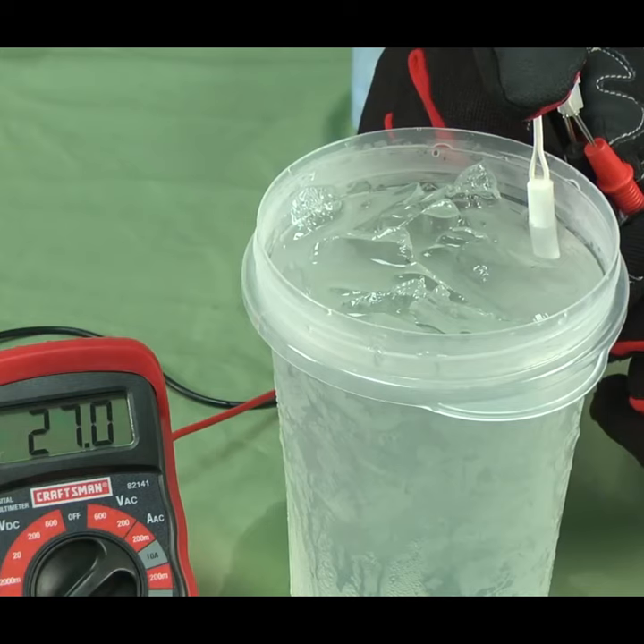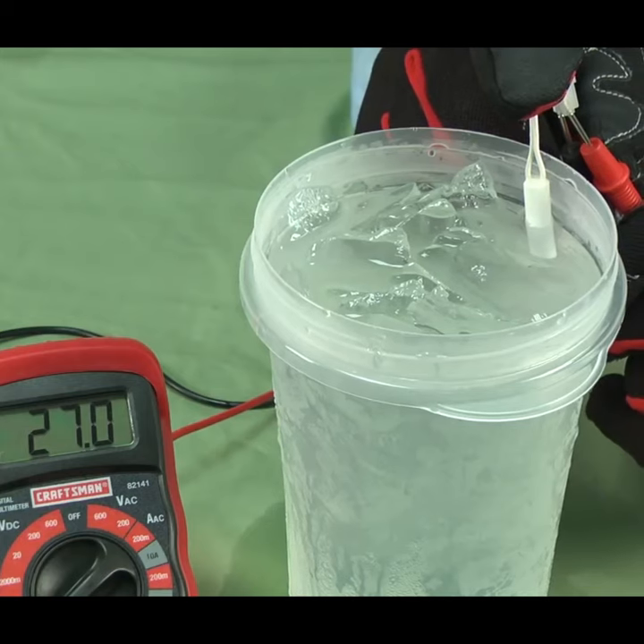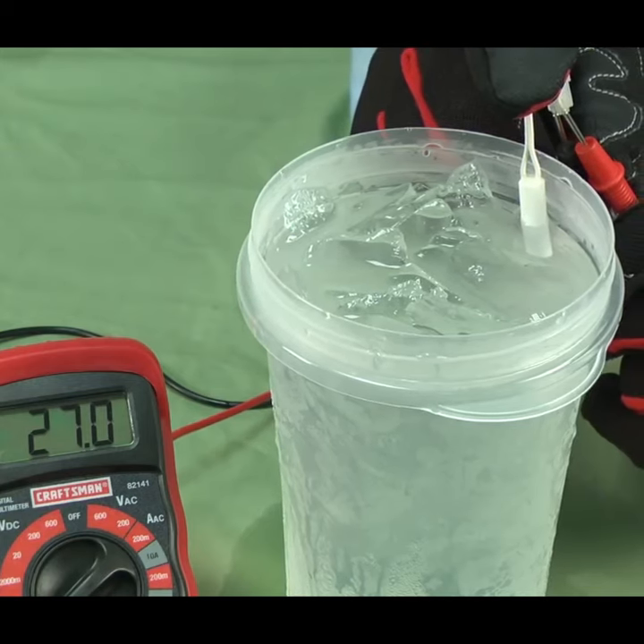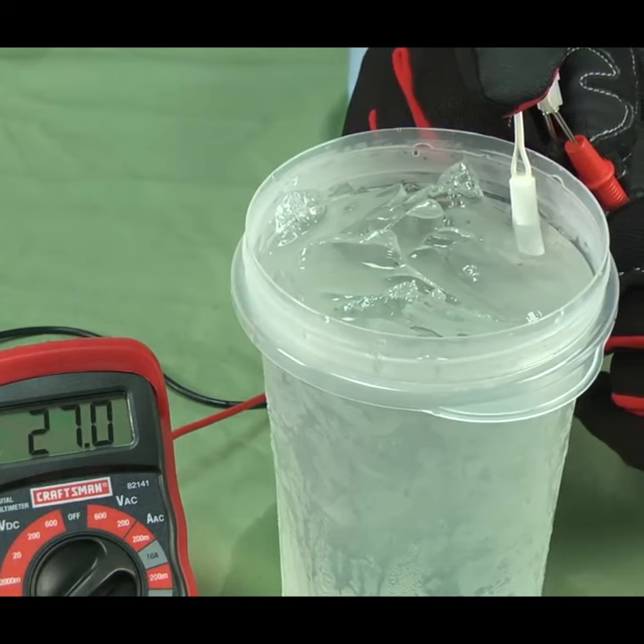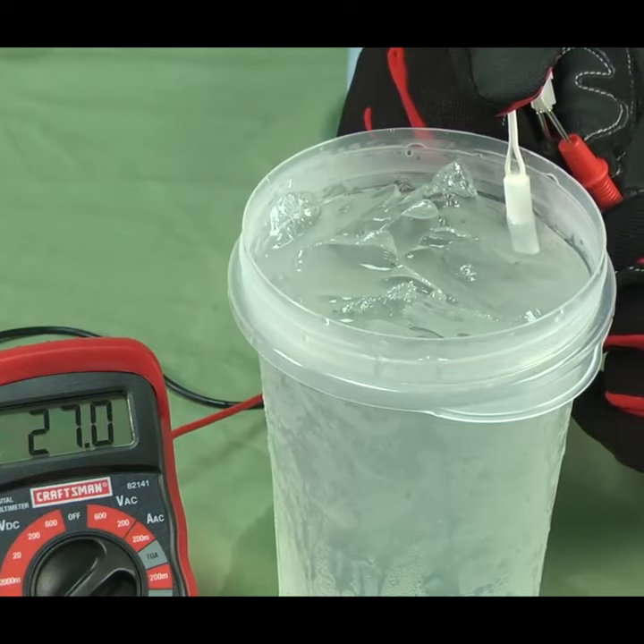Place the thermistor in a cup of ice water and you should measure around 27,000 ohms of resistance because the water temperature is around 32 degrees. Replace the thermistor if the resistance readings are off by more than 10 percent.